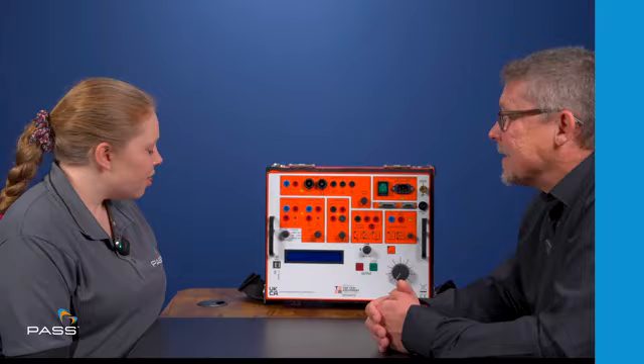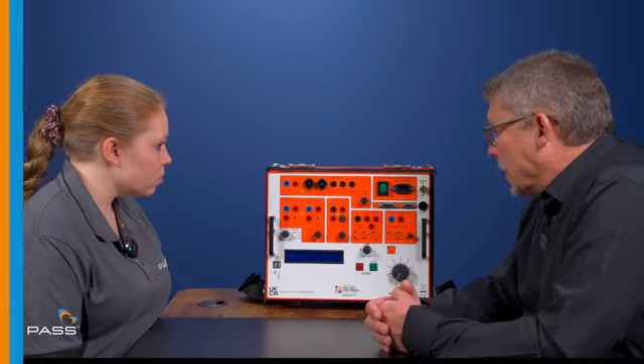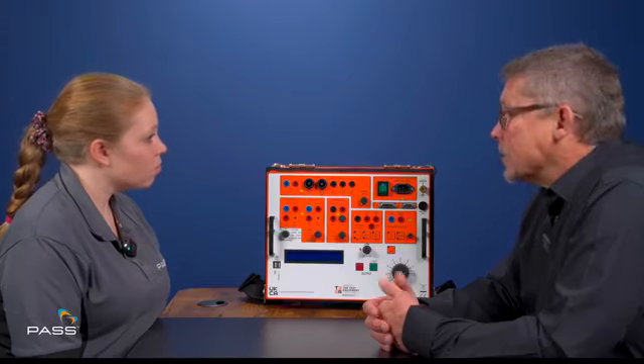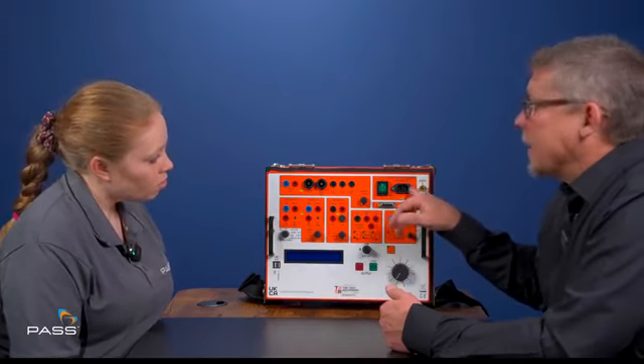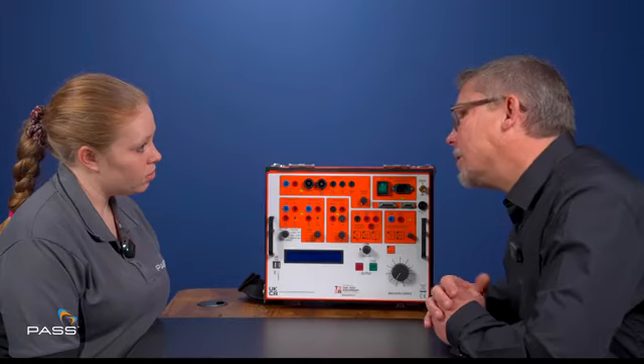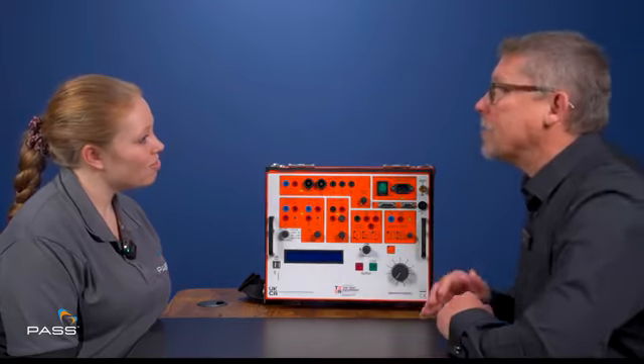It does come with a metal case or a Peli case, doesn't it? Yeah, when you buy the unit, the only choice we give you, some manufacturers, as I alluded to earlier, they'll ask you, do you want 240 volts or do you want 110? And you have to pick. And if you've picked the wrong one, that means you go to a sub and go, well, can't do the testing. They'll ask you, do you want 50 hertz or 60 hertz? That's okay if you're in America or the UK. But if you travel the world doing commissioning, well, you might need a number of different sets, and make sure you take the right one with you. This one, just one does all.